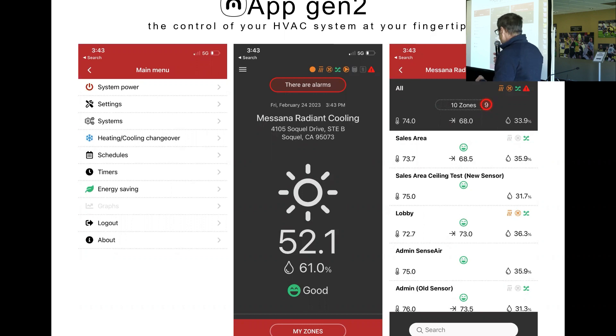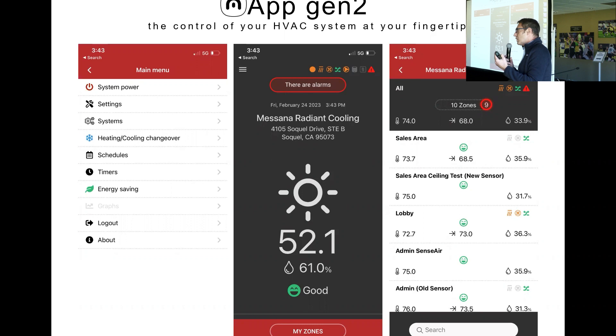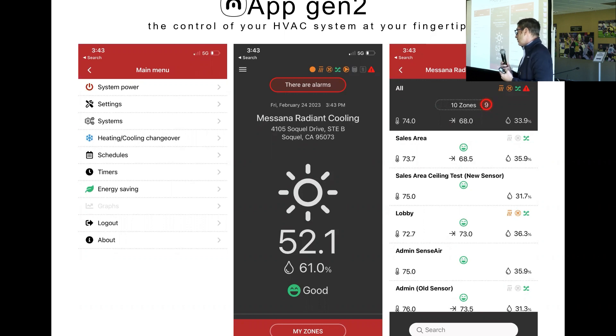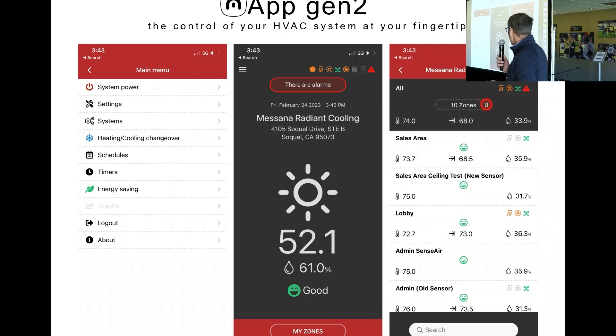There is a nice graphic option where you can build graphs and see temperature during the day. As an installer, you can go really deep to do troubleshooting — seeing temperatures in the mixing valve, supply, buffer tank, and heat pump. If something is not working, you can customize a graph and understand, for example, that the heat pump is mounted incorrectly or not working properly. All troubleshooting can be done using the graph platform.